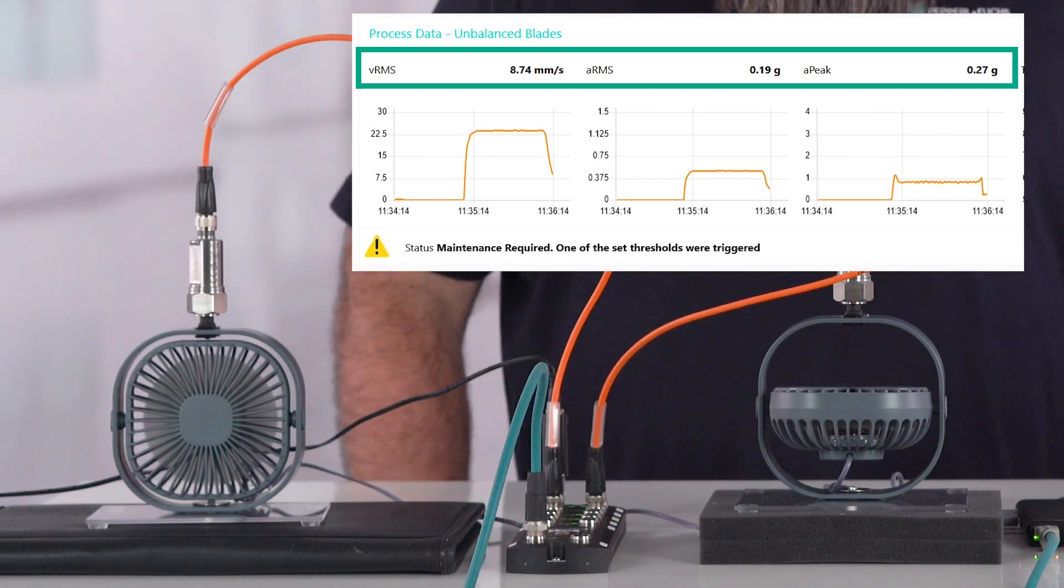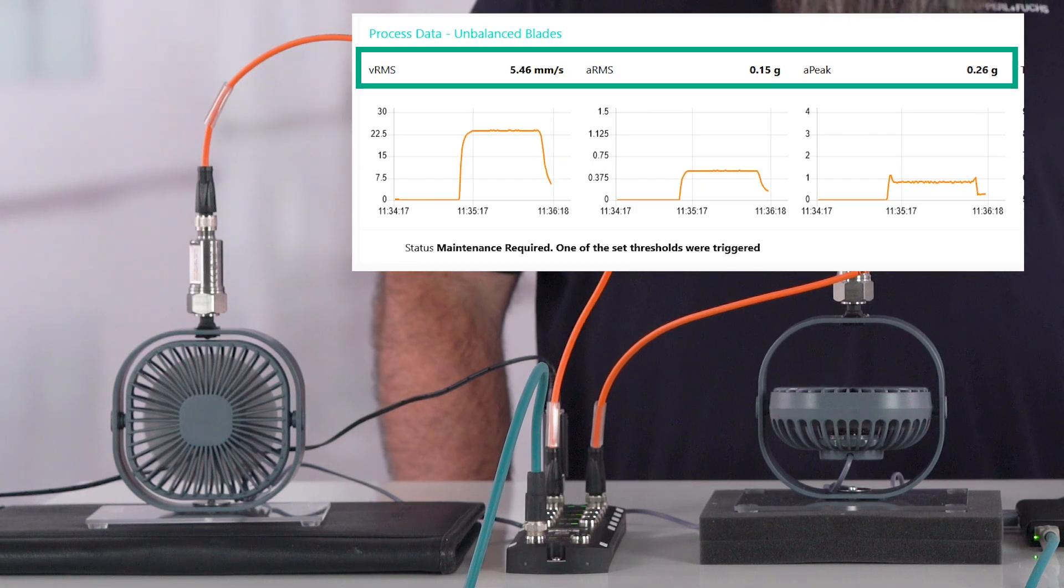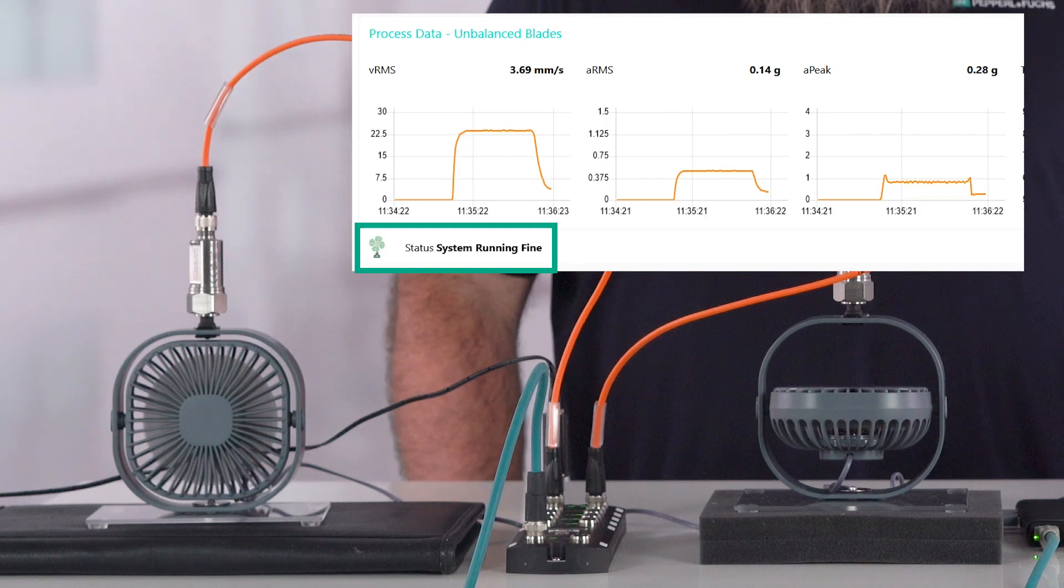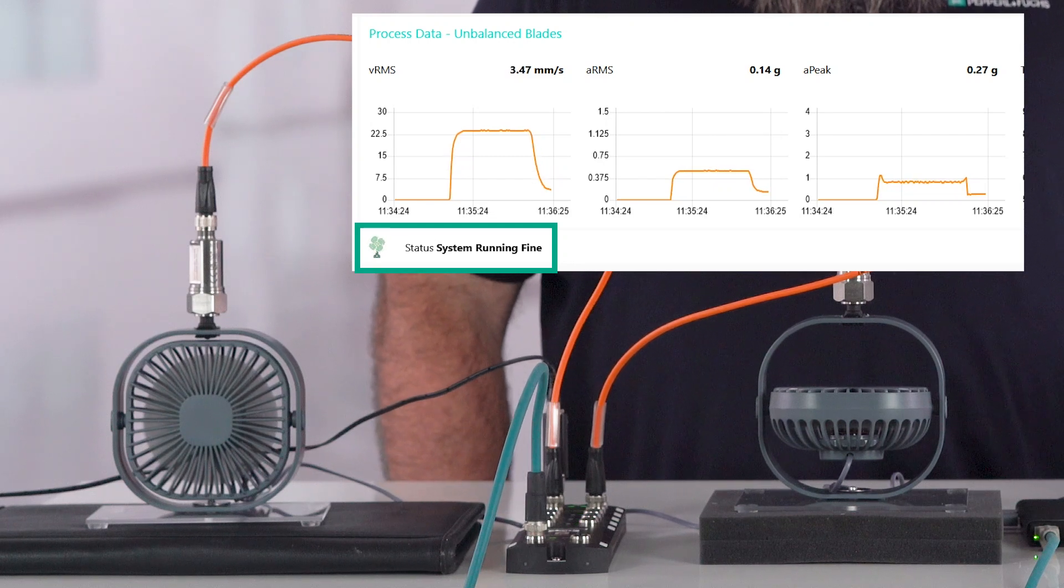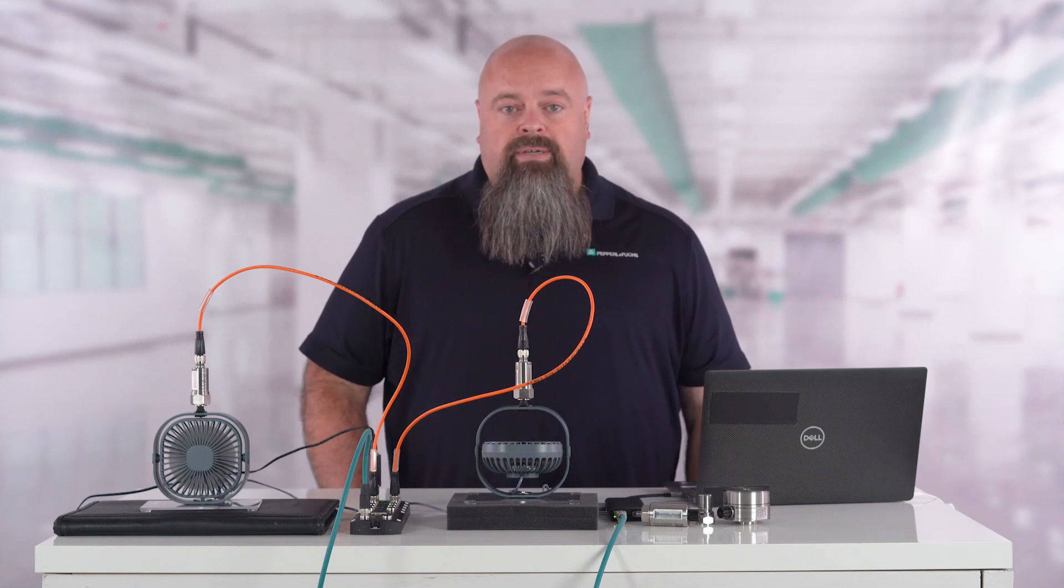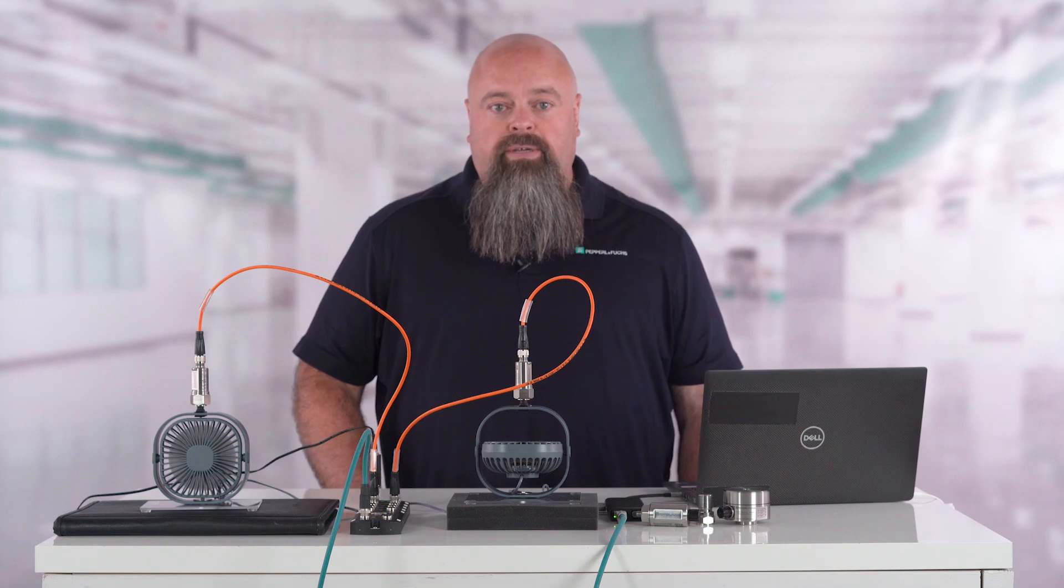You can see the values for Sensor 2 have decreased, even to the point where the fan appears to be running within normal parameters, and the warning icon has returned to the fan icon. This demonstrates the need to mount the sensor in the proper axis. This also shows that a single-axis sensor can isolate the vibration profile of the rotating shaft from the rest of the machine vibrations.